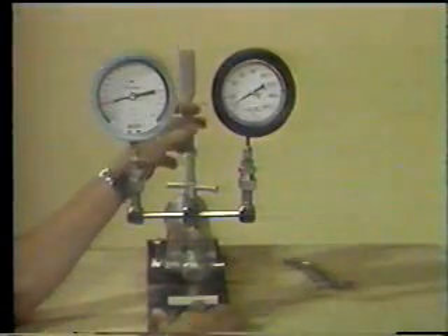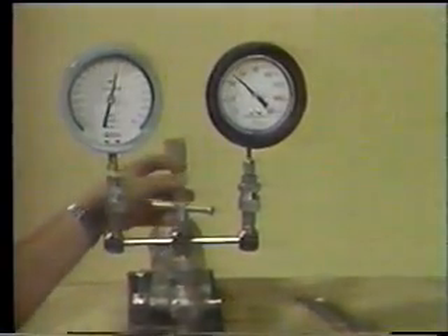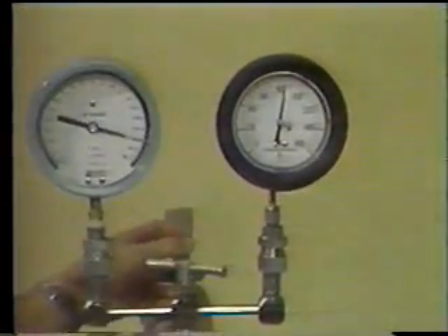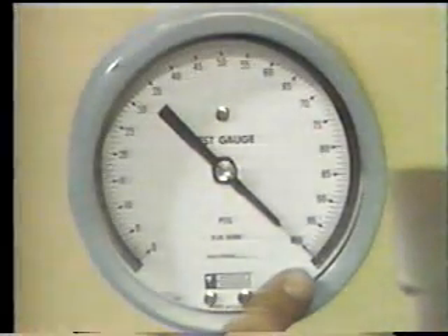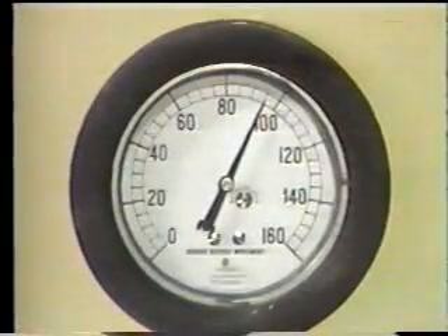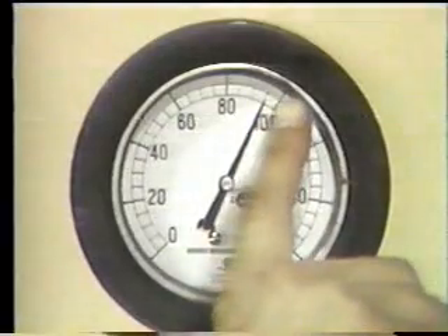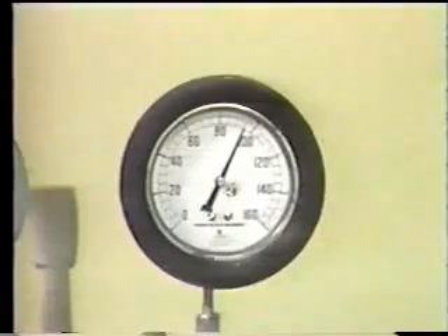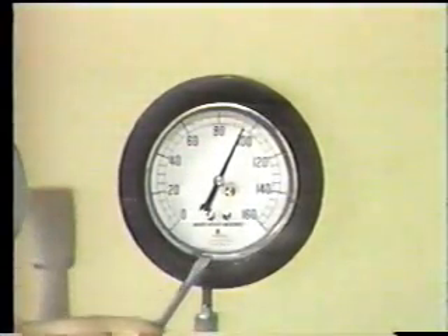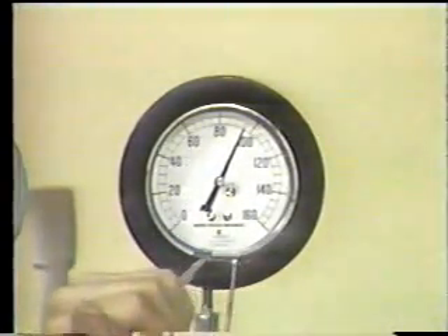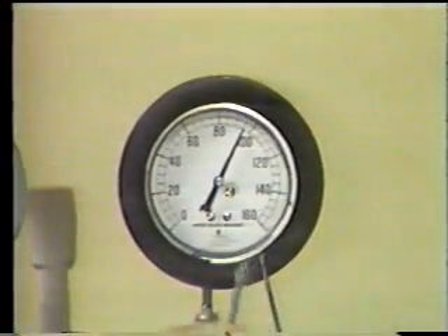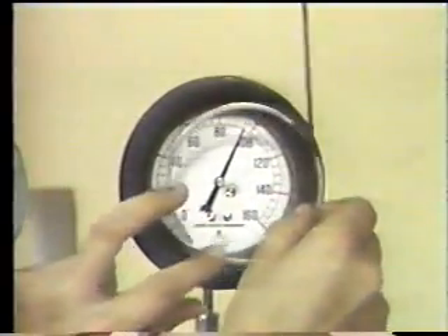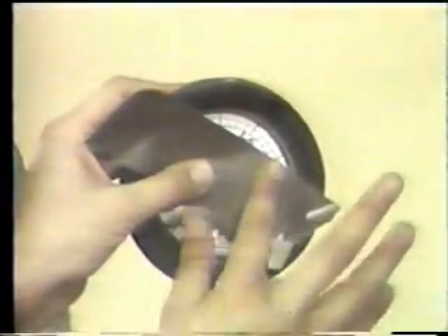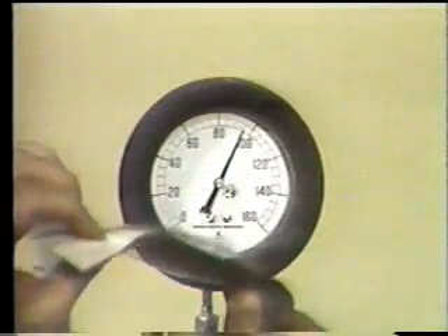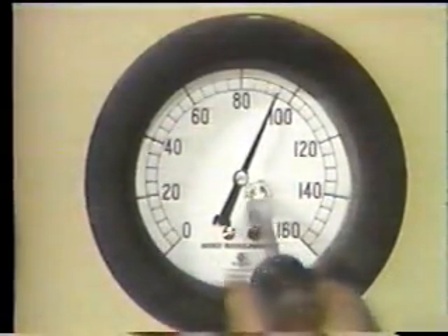Using the pump from the dead weight tester, pressurize both the master test gauge and the gauge to be calibrated. Once the master gauge indicates operating system pressure, check the indication on the panel gauge. As you can see, the panel gauge is out of calibration and must be adjusted. To do this, we must first remove the retainer, being very careful not to damage the gauge glass. Next, apply tape to the glass and carefully remove it from the gauge. Now use the calibration screw to correctly set the gauge.